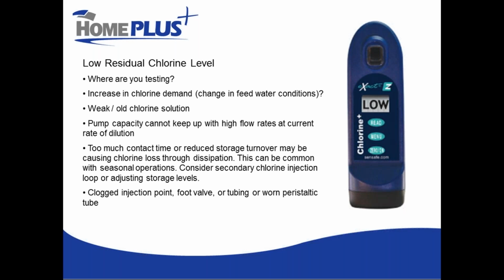This is not a really common problem, but it's more common in a system that's undergoing some level of expansion. So you used to have 10 homes in your mobile home park. Now you've added another 10 and you're serving 20. Now with that additional flow rate, you need a pump that has higher capacity. So some pumps you can increase the capacity by changing the peristaltic tubes in them. Some you might just have to replace the whole pump, or you could reduce your dilution and see if at a reduced dilution the pump can keep up.